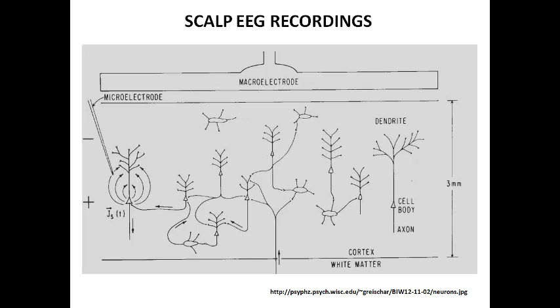The first important requirement for EEG is electrodes. Electrodes are the primary source for picking up the electrical activity of the brain. An electrode is a small metal disc, normally made of stainless steel, tin, gold or silver, covered with a silver chloride coating, so that it is very good at conducting.